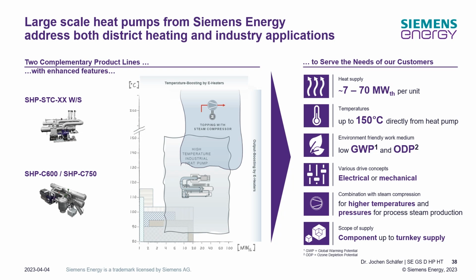Moreover, we have an in-house portfolio for steam compressors, and using the steam compressors we can further increase temperature and pressure to about 55 bars and 270 degrees C. So in summary, we start at about 7 megawatt, we can go up to 70 megawatt with a single unit, and up to 150 degrees C with our regular high temperature heat pumps.